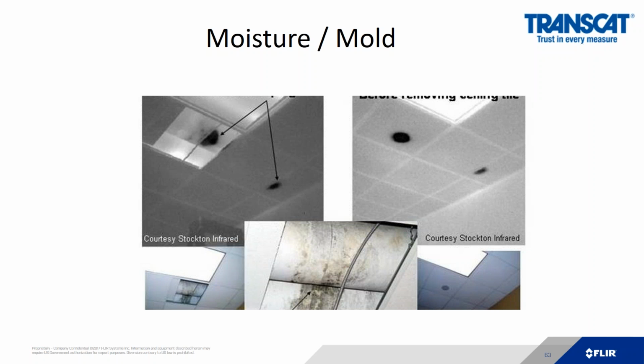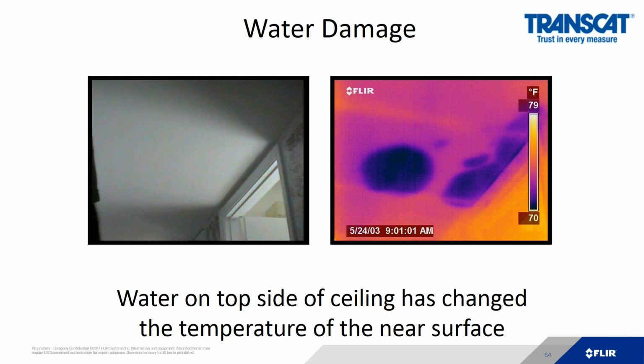I get this question all the time. Will an infrared camera see mold? It will not. An infrared camera cannot detect mold. What it can detect is the presence of water, as we just described. So in this, you can see the ceiling tiles, the cold, dark spots is water that's evaporating. Here's another example of water on a ceiling. If you look closely, under the FLIR logo in the upper left-hand corner, you see this yellow stripe. That is the ceiling joist between the first floor and second floor. But we can clearly see where there's water in this picture.